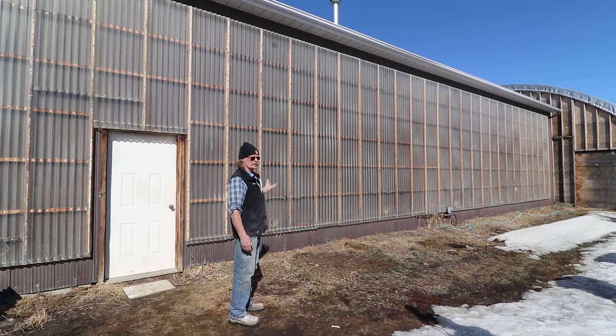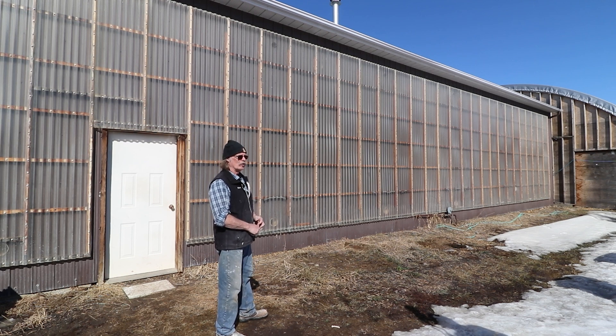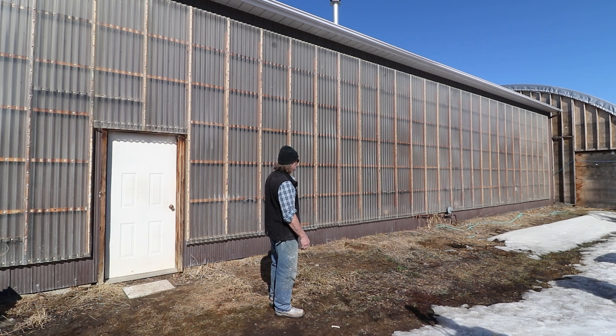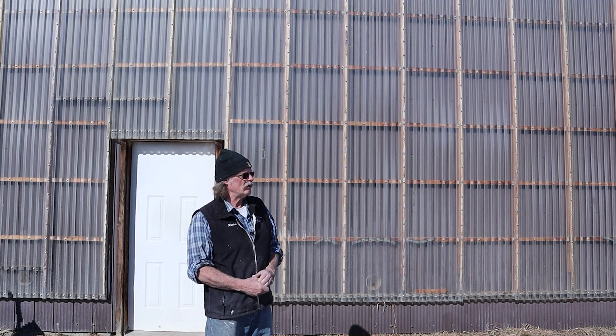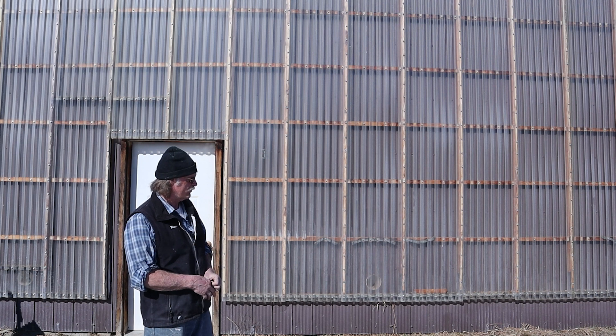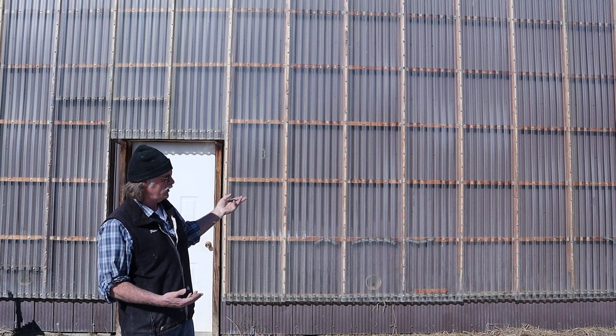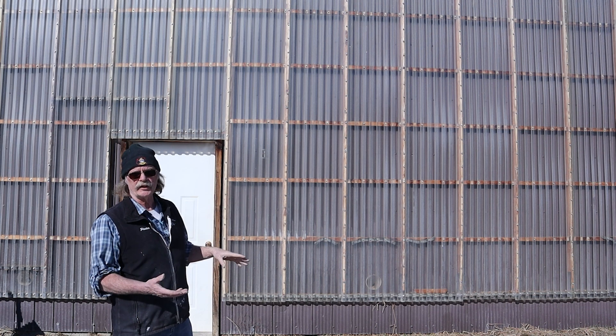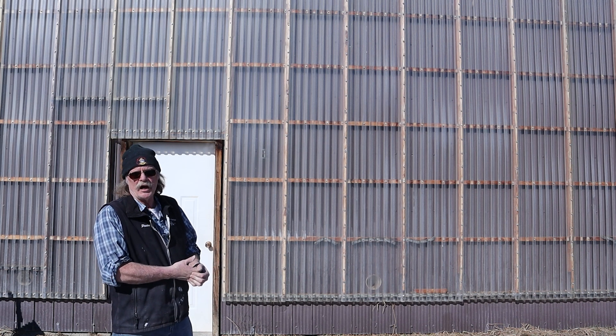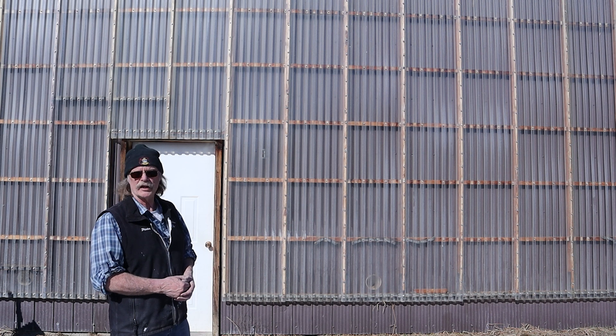The sun actually heats this 40 by 60 foot shop, which is not very well insulated — not around the plug-ins, overhead door, or walk-in door, and it doesn't even have house wrap. The ceiling is insulated well and there are no windows, which reduces heat loss. If I were to redesign, I would direct the collected heat into a perforated four inch pipe into a gravel bed for thermal storage. As long as you have 700 square feet on the south wall facing the sun in Alberta, you're going to be fine.